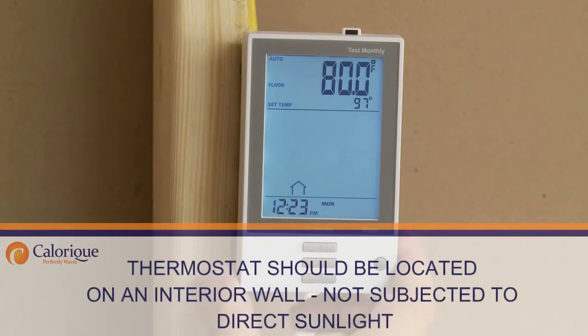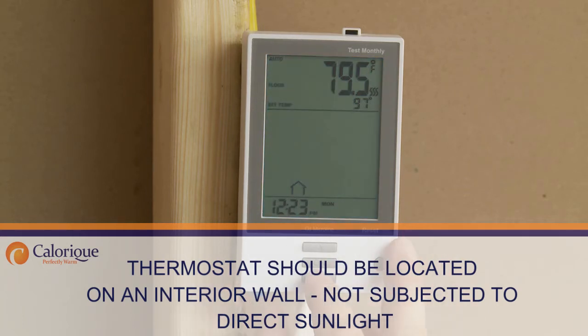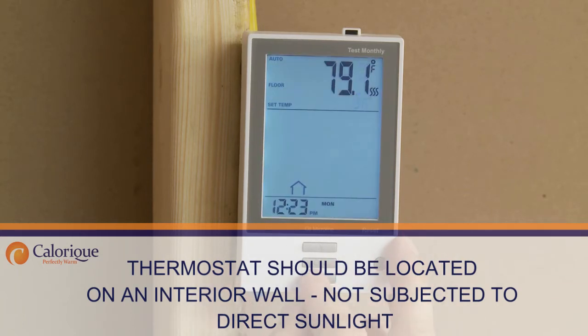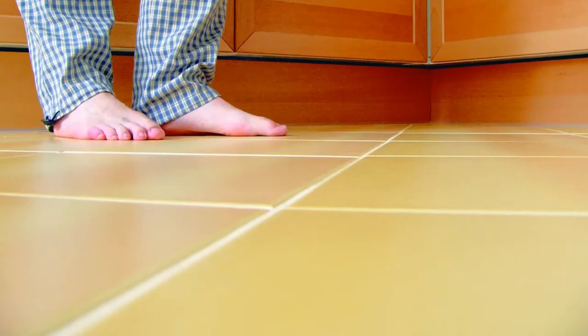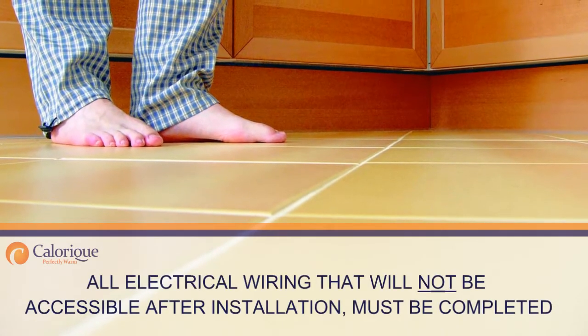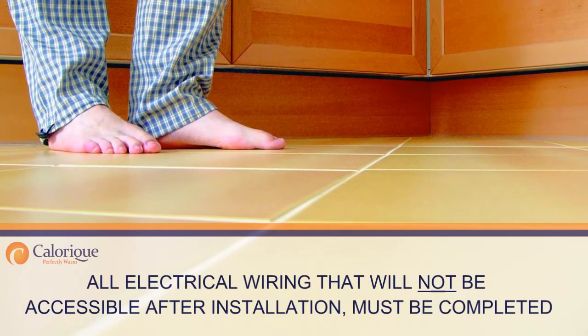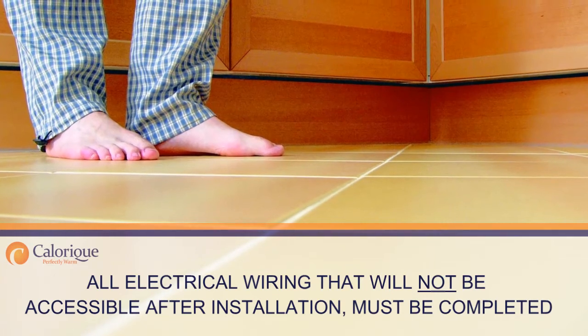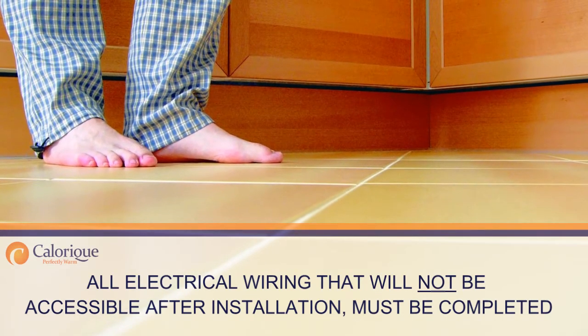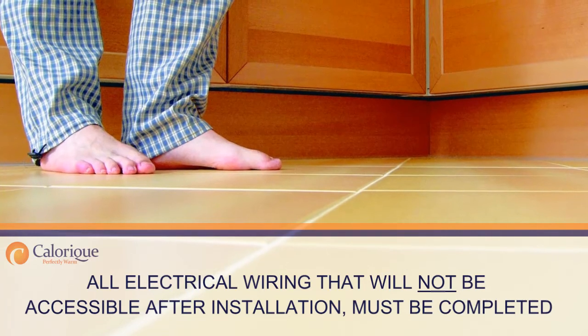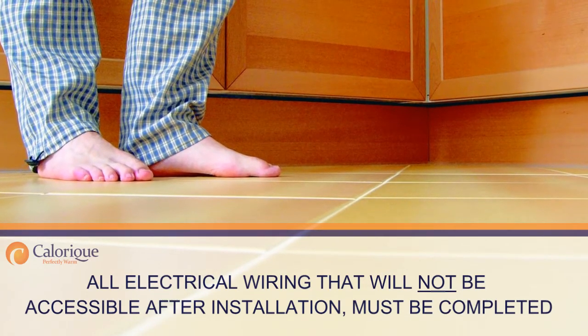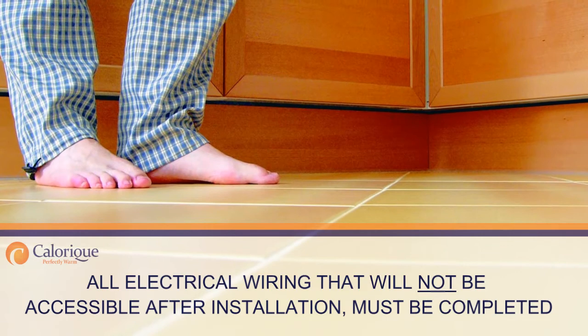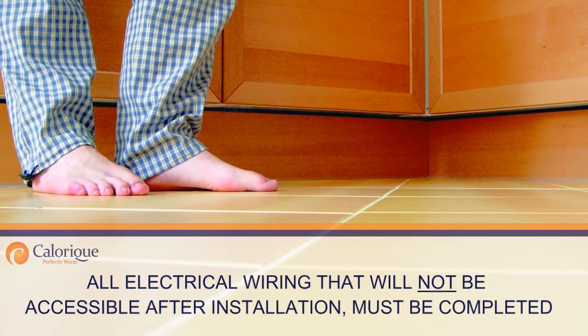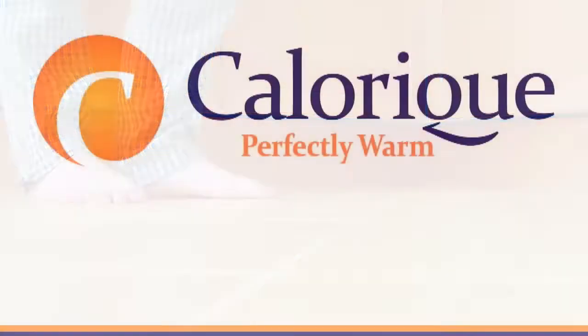Note that the thermostat should be located on an interior wall where it will not be subjected to direct sunlight and that the length of the non-heating leads is taken into account. Please ensure that non-heating leads will not cross over any heating elements. Before work can proceed, all electrical wiring that will not be accessible after installation of the heating system must be completed. This may require coordination with the electrical contractor.